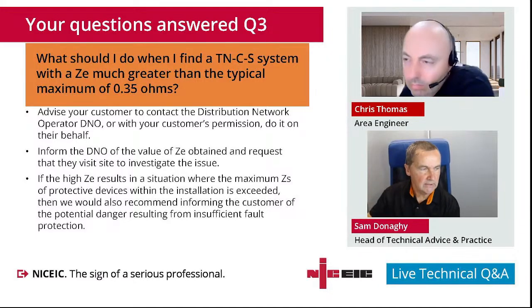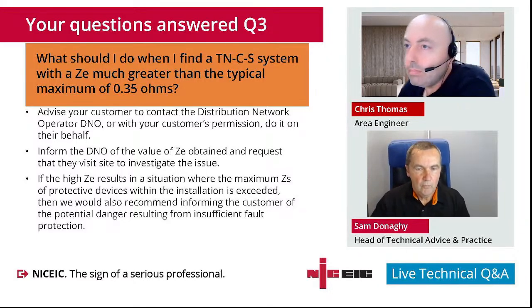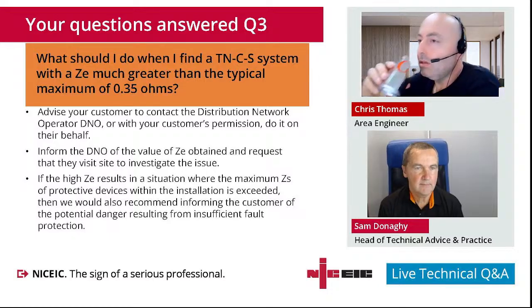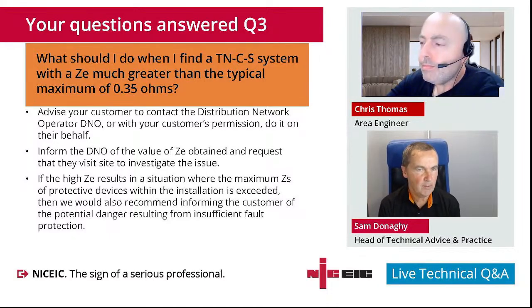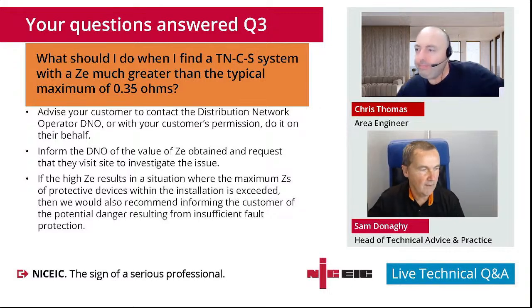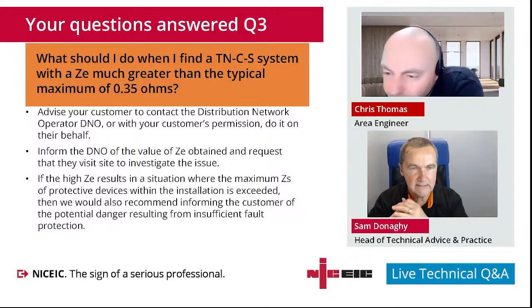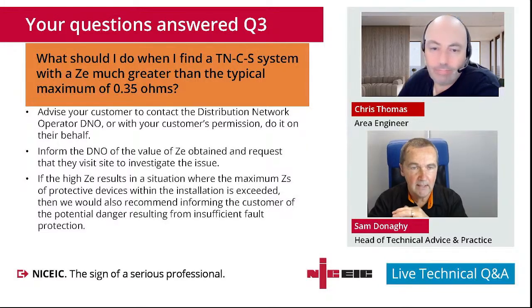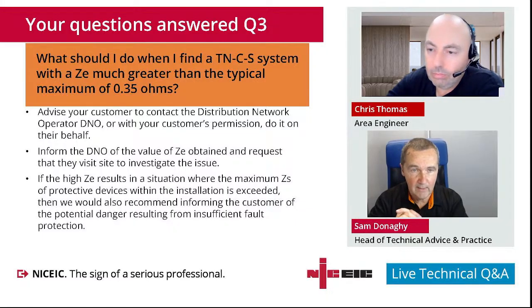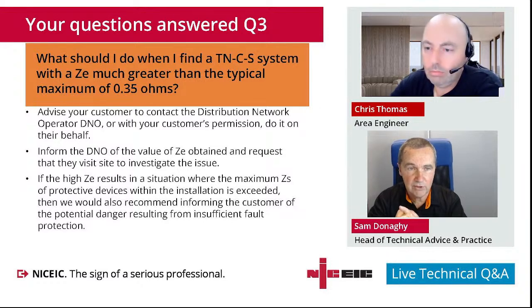So another held over question is what should I do when I find that a TN-C-S system has a Ze which is much greater than the typical maximum of 0.35 ohms? Again, it's a common question to the technical helpline, and it's 0.35 for TN-C-S, but we get the same issues with 0.8 on a TN-S. So the first thing we always recommend is that you advise your customer to contact the DNO network, or with your customer's permission, do it on their behalf to let the DNO know what the issue is.